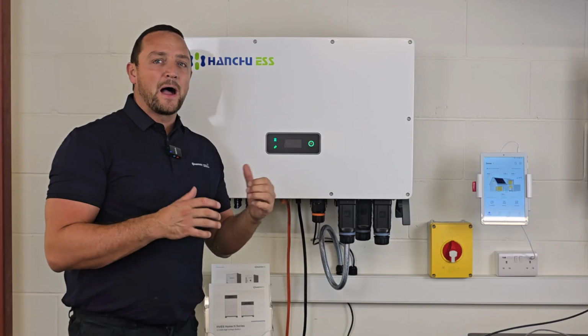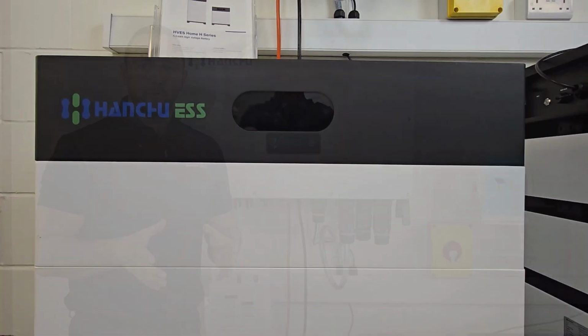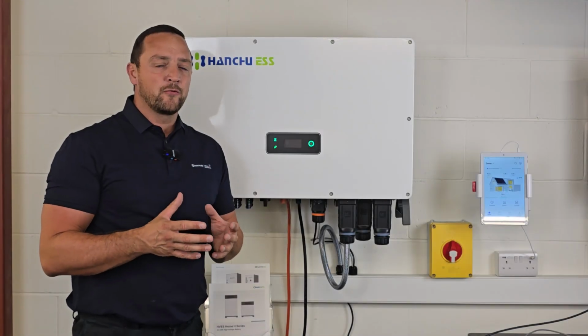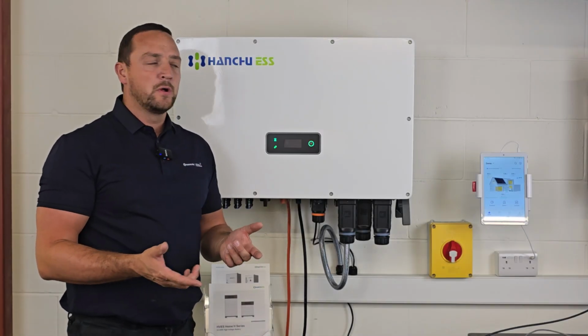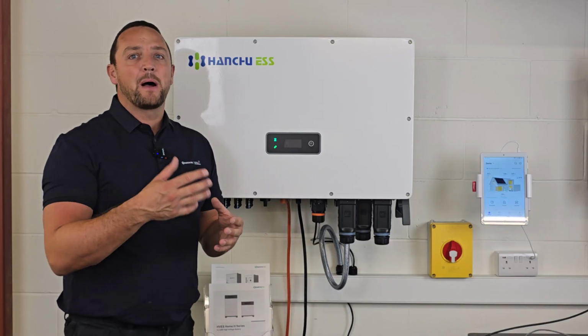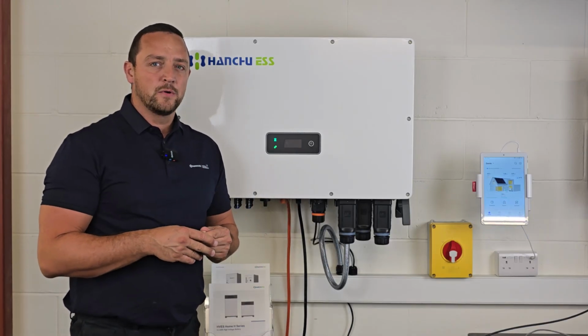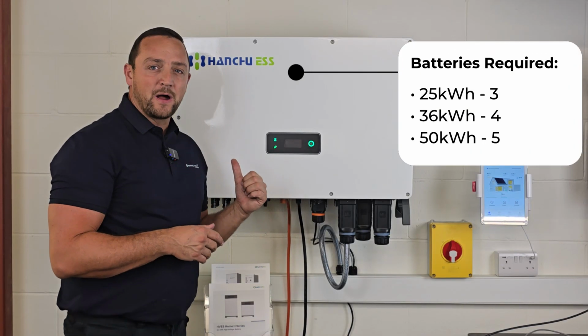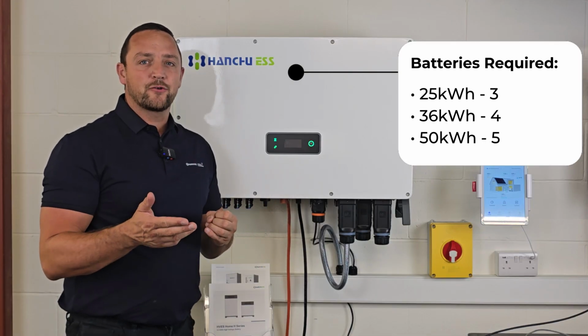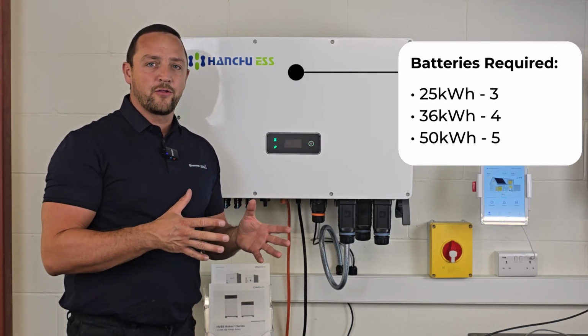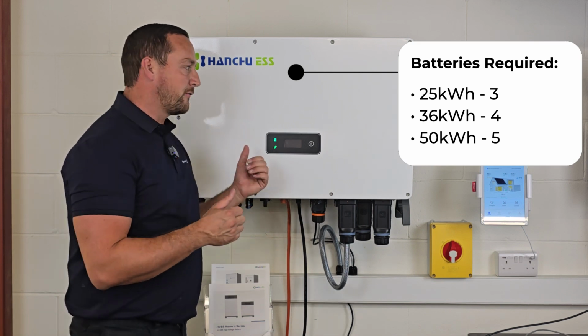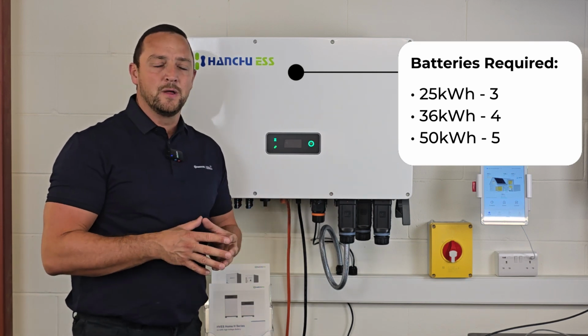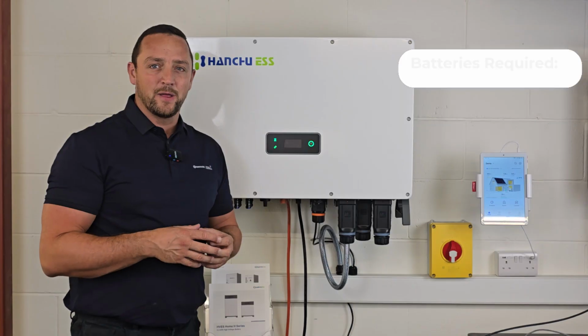Each one of these units though is compatible with our HANCHU 9.4 blade lithium high voltage batteries. So you do need a minimum number of batteries to achieve the maximum charge and discharge rates or power backup in the event of a power cut. So if it was a 25 kilowatt unit, you would need 3 batteries, 4 batteries for the 36 and 5 batteries for the 50 kilowatt to get the maximum discharge rate through that EPS.